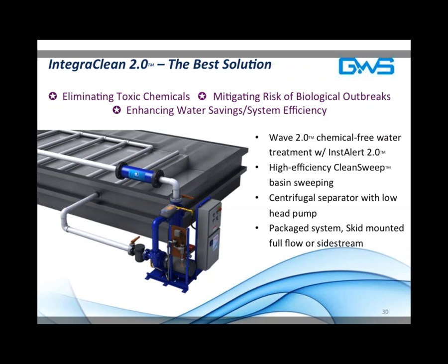Thank you. Can the system be used for boiler systems? It's a good question. You know, the predecessor to Wave used to be used in boiler systems. There's a bit of a conundrum with that, though, because most boiler systems will use softeners to remove the calcium carbonate. When you remove the calcium carbonate, you pull out the majority of the elements or minerals in the water that one would be precipitating. So it's not really advised, and it's fairly redundant in cases like that.